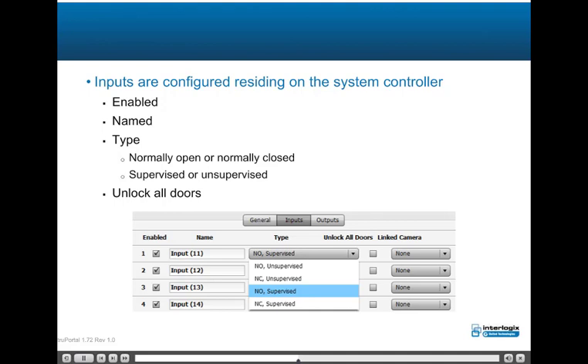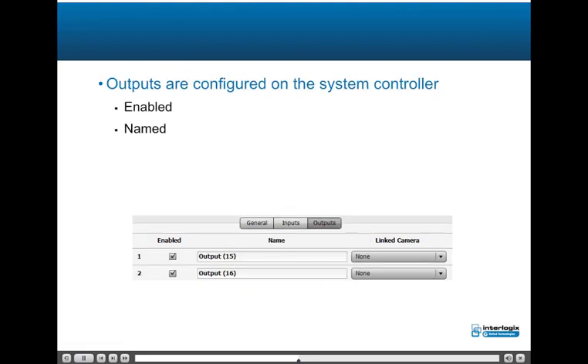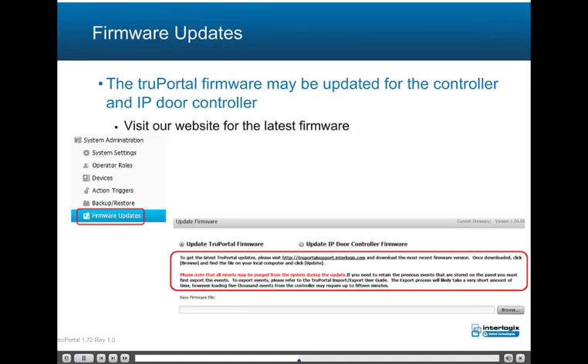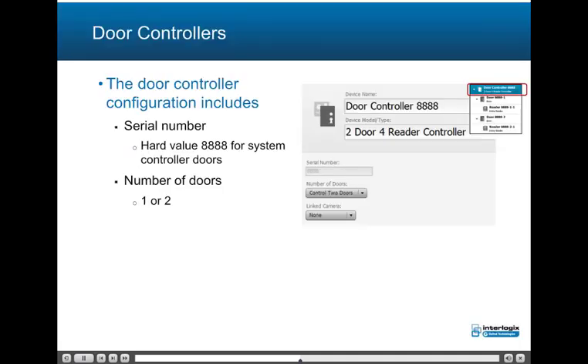Outputs are configured on the system controller and may be enabled and named. The truPortal firmware may be updated for both the system controller and IP single-door controller; visit the website to download the latest firmware revision. Be sure to export any historical events residing on the system controller prior to updating the firmware. Door controllers consist of either doors on the system controller or remote door controllers on the SNAP bus or network. The serial number is required to configure a remote door controller, which can be found on a sticker on the door controller board.